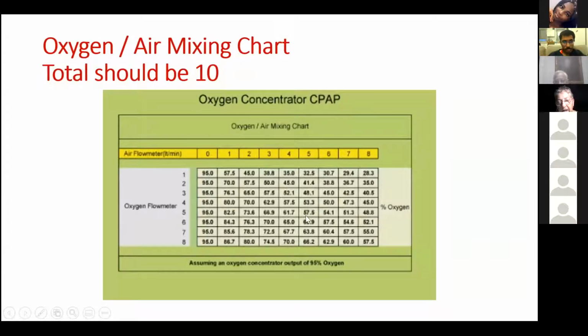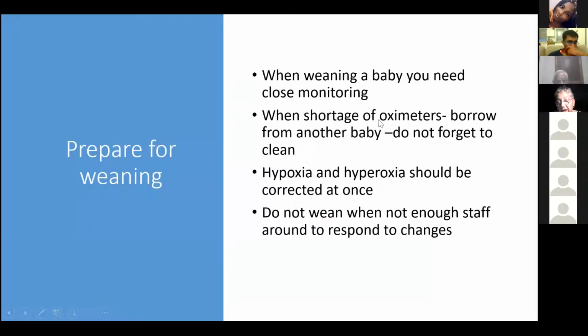So this table gives you the combination of flow of the air and the flow of the oxygen to choose the right amount of oxygen needed for this baby. And we will take some examples of the babies that you have sent me as cases in your MBU. So when you prepare the baby for weaning, you have to make sure that the baby is monitored properly. If you don't have a free oximeter, you have to borrow it from another baby, because you cannot wean a baby if the monitoring is not continuous, because hypoxia or hyperoxia have to be immediately managed as needed. So do wean only when you have enough time to look at the baby and there is experienced personnel around.